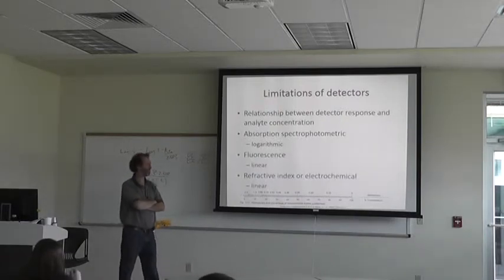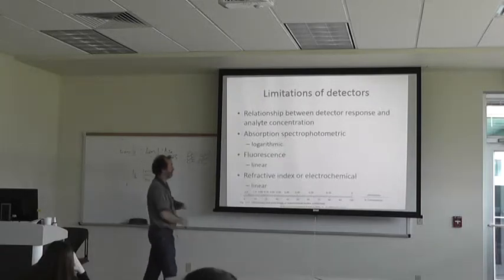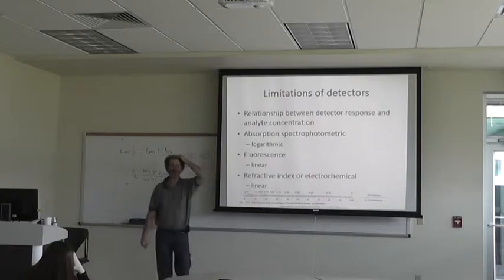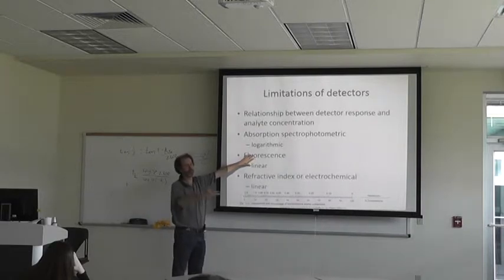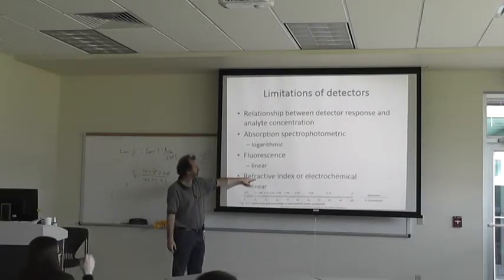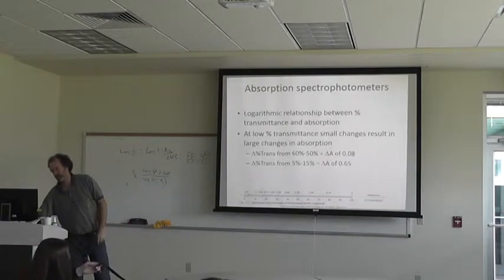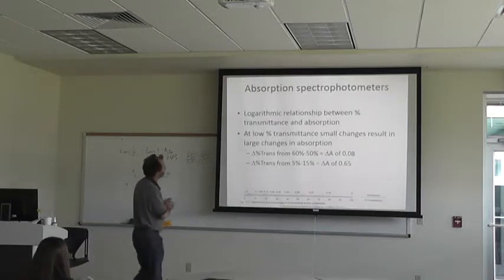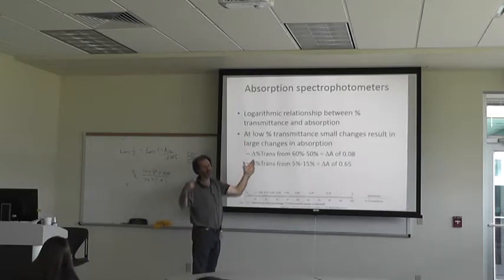If it's really high or really low, the logarithmic scale makes it problematic. Fluorescence is linearly related — the amount of light being shined versus the voltage, because the detector detects the light and that amount of light is proportional to the voltage signal. Refractive index and electrochemical are also linearly related. For the absorption spectrophotometer specifically, there's a logarithmic relationship between percent transmittance and absorbance, because what the machine reads is the percent transmittance.